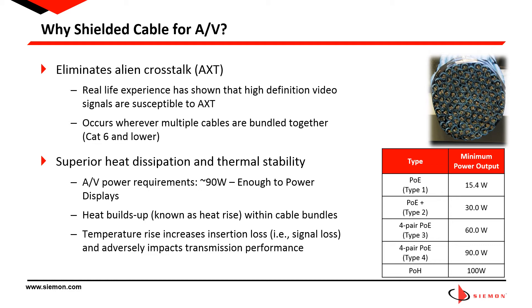Fortunately, Siemon has been a long-standing advocate for shielded cabling systems. We know that our shielded systems offer optimal resistance to alien crosstalk as the shield prevents alien crosstalk from affecting adjacent cables. All of these applications are using remote powering to power their devices, which is a key reason for deploying Category 6A shielded cabling at a minimum. With the release of the IEEE 802.3BT Power over Ethernet or PoE standard in 2018, we now have five different levels of remote powering ranging from 15 watts up to 90 watts for PoE and 100 watts for Power over HDBaseT, where the higher wattage is capable of supporting TVs, digital displays, and even desktop computers.